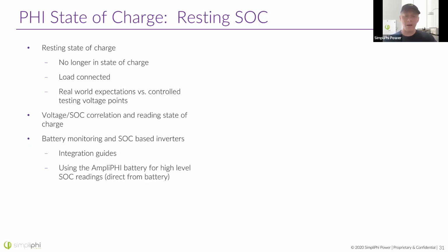So our AmpliPHI batteries do have this built in inside of the battery. The BMS will take care of these readings and report them to your inverter. So you have to use a communicating inverter to get these readings out of the battery. Whereas our standard Phi battery does not have this capability. There's no such battery monitor inside the battery, so you're going to need to add an external battery monitor and then program that monitor accordingly.